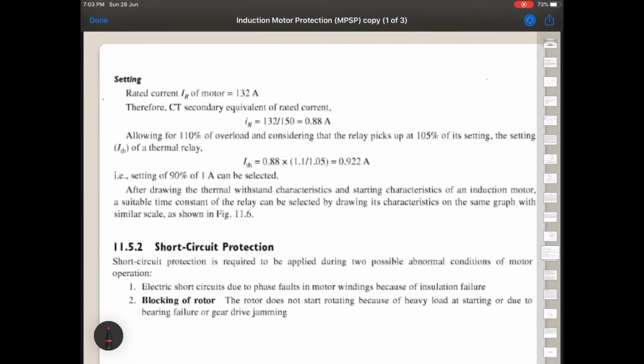Now we'll see the setting of it. The rated current of the induction motor is 132 ampere, which we have seen. It's a secondary equivalent because primary is 150 and secondary is 1 ampere. If you consider the secondary equivalent, we get 132 by 150, which is 0.88. Now as was said, overload can be allowed up to 110% of this current, and because of that we are multiplying 0.88 with 1.1.